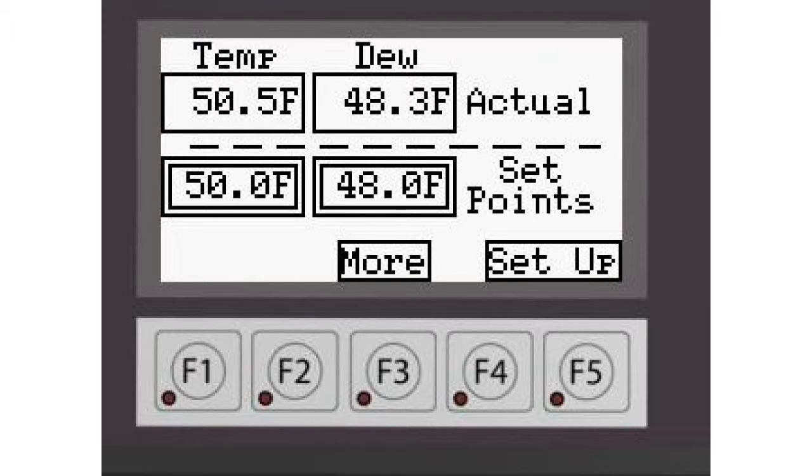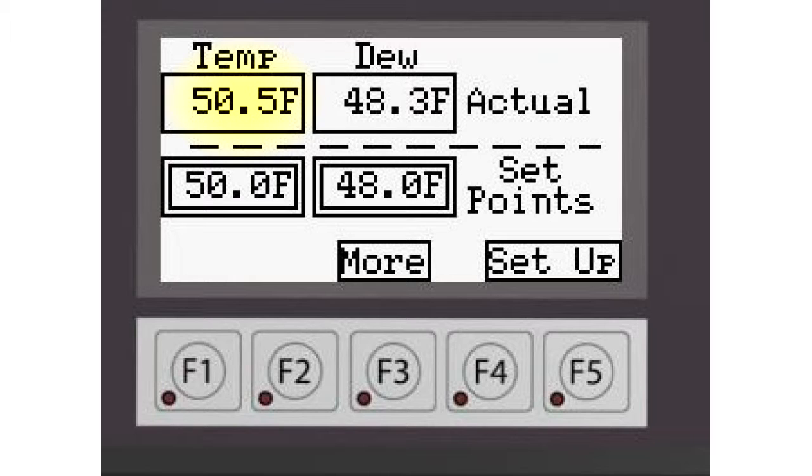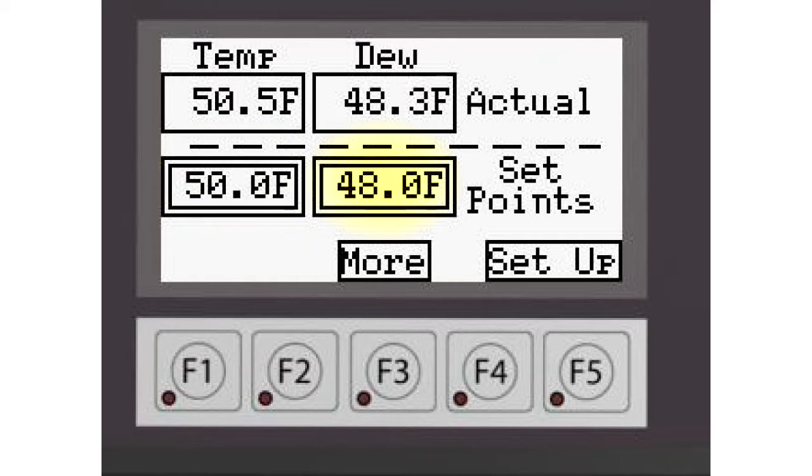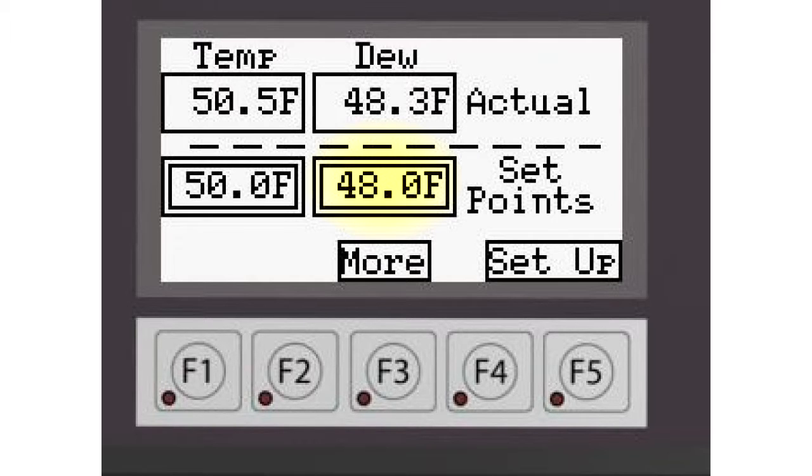Once you see the screen, you'll see on the upper left the current dry bulb temperature in your room. To the right is the current dew point temperature in your room. To the lower left is the dry bulb temperature that you are looking for the room to be maintained at. To the right of that is the desired dew point temperature you're looking for the room to be maintained at.